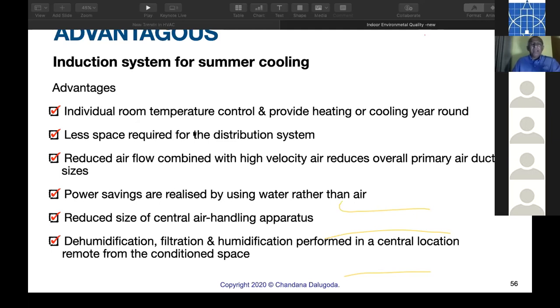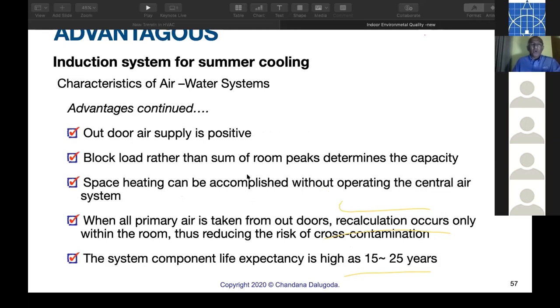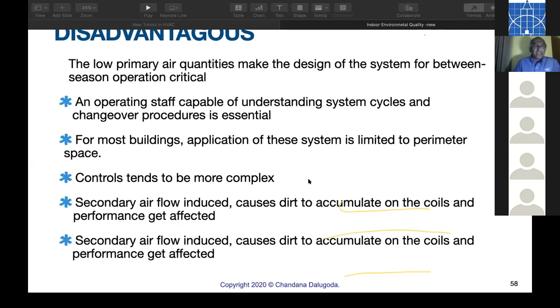Outdoor air supply is positive. Block load rather than the sum of peak determines the capacity. Space heating can be accomplished without operating the central air system, only sending hot water. No AHU is required. When all primary air is taken from outdoors, recirculation occurs only within the room, thus reducing the risk of cross-contamination. Good answer for patients' rooms, COVID-19, all that. The system component life expectancy is 15 to 25 years, but there are disadvantages.